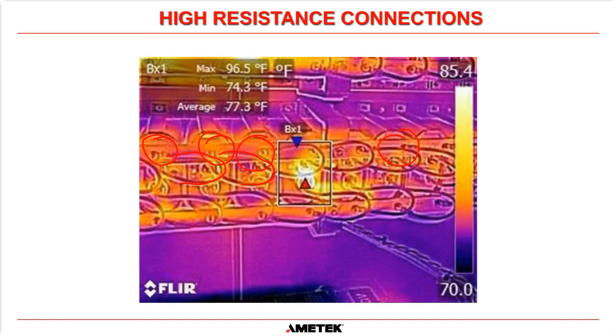And everything looked okay from a visual inspection standpoint, but you can see from this picture that our camera pointed out that this connection here is actually at 96 degrees, 20 degrees above the average temperature of this whole capacitor bank. So we knew there was something wrong there. So what happened was the field service engineers shut down the UPS and made sure that all the energy had been taken out of these capacitors, and then did a closer visual inspection. And what he found was one of the connections on that capacitor, although it seemed like it was pushed on to the correct crimp terminal, it was actually slid to the side of it, and it was just making a very light connection, and you could see it was heating up. So he had to remove it and put it back on again, and everything was fine from that point there.